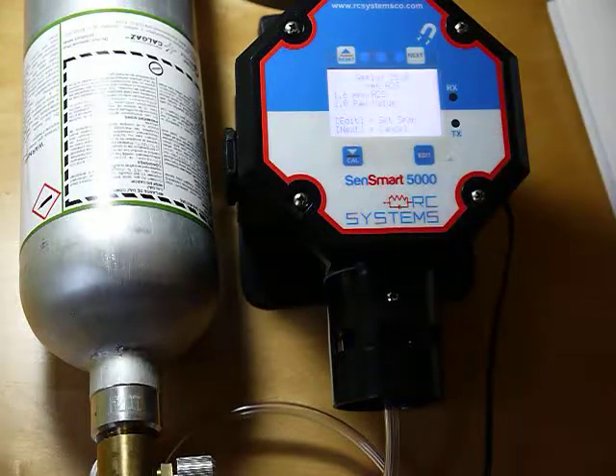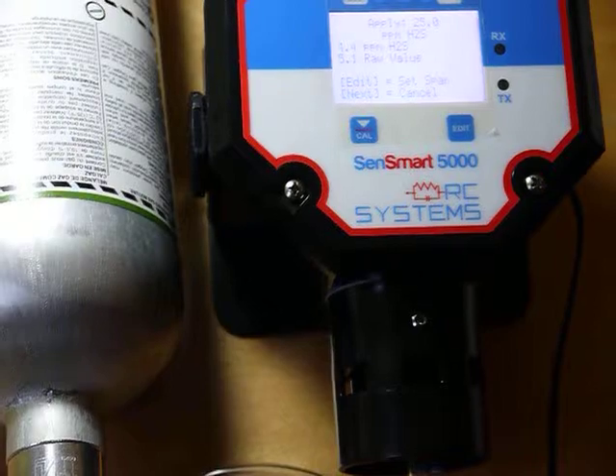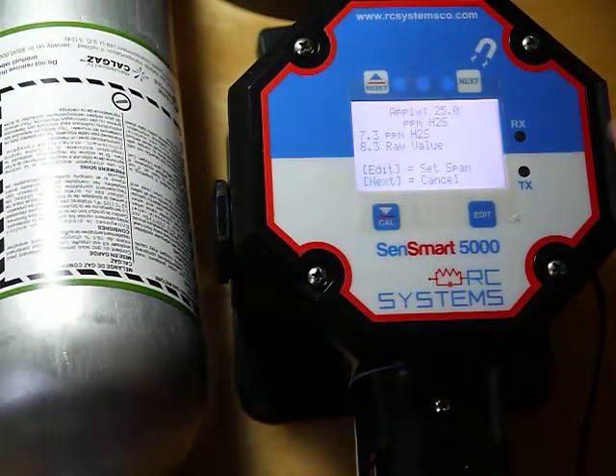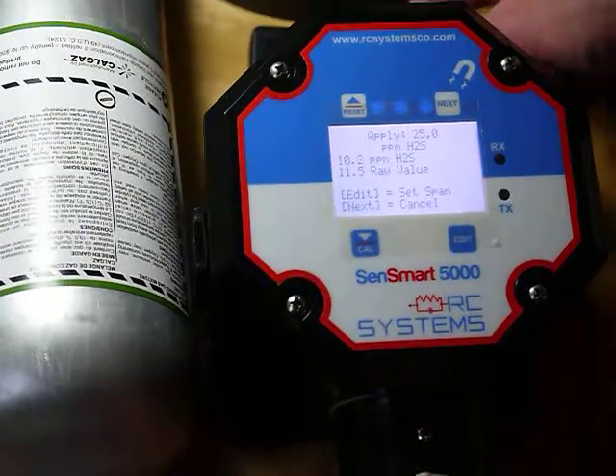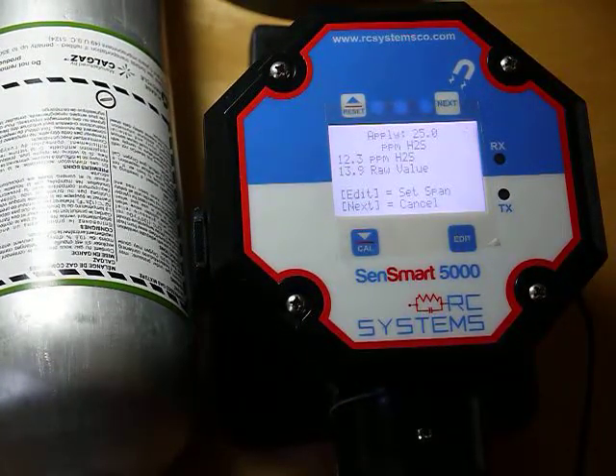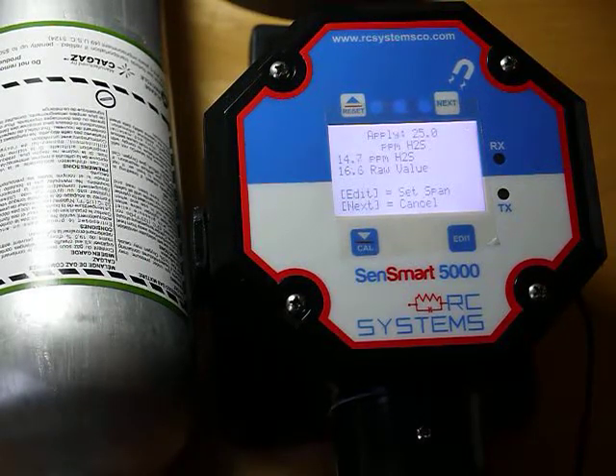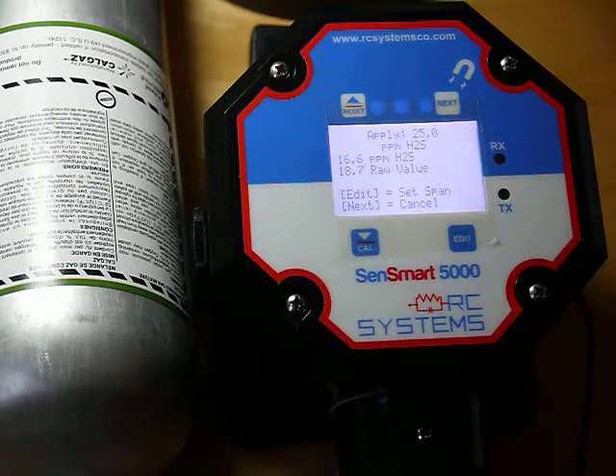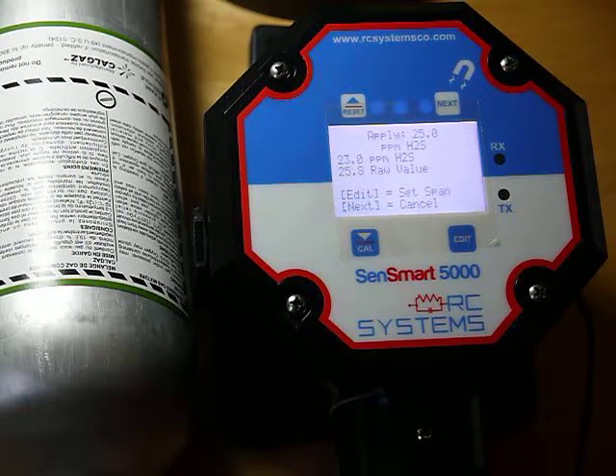And this is nice. I can see the value start to roll up. So I can watch that. It's at 7. Actually, now it's up to almost 13. Yeah, over 13 now. So the idea is to apply the gas and let the sensor stabilize, and when it's stable, to use the magnetic wand and hit edit to lock that value in. Now this transmitter should technically have been powered on for maybe a couple of hours to stabilize. But we'll just do this and see how close we come to it.